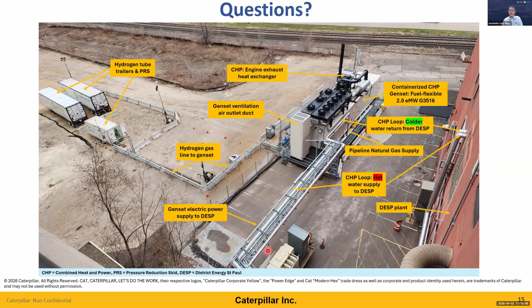Based on our single cylinder engine testing, we did look at the combustion components like the piston and liner, cylinder head, etc. That runtime was about 500 hours, and we didn't really see any impact of running on hydrogen there. We are looking for opportunities to run this genset for longer hours, up to 1,000 hours. Then we plan on taking different parts that came in contact with hydrogen for long duration and inspecting those to see if there is any impact of running on hydrogen. We do not have that data fully yet.